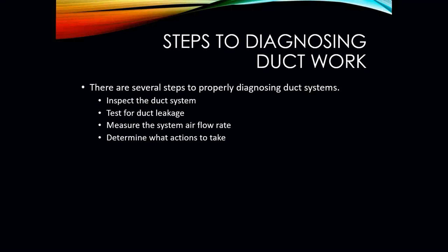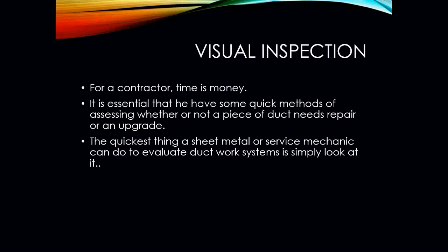Then after all that, we are going to determine what actions we need to take. Does the ductwork need to be redone? Does the ductwork need to be resized? Do the dampers need to be adjusted? Does the blower need to be sped up? Does it need to be slowed down? Does the blower need to be cleaned? Does the filter need to be cleaned? And so on and so forth. All of these things affect how a furnace or air conditioner is going to work. Is it going to be working efficiently and quietly? For the contractor, we all know it.